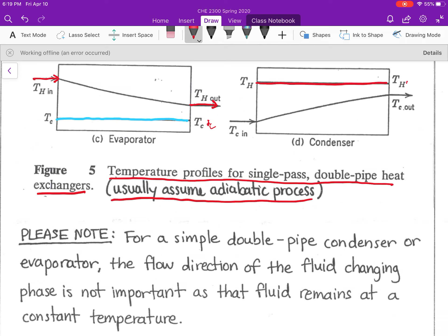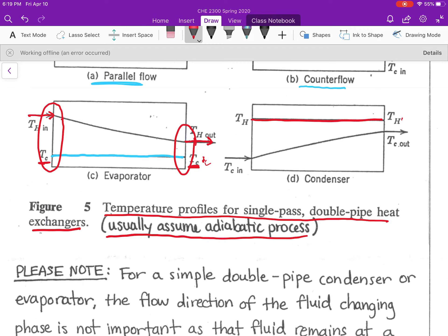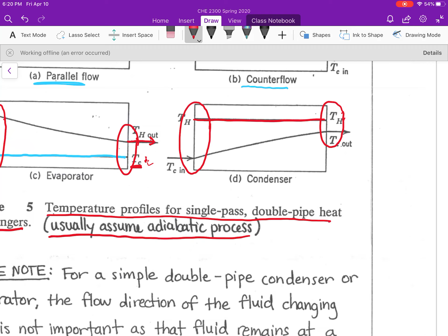It's not important because that fluid remains at a constant temperature. Regardless of what direction the cold fluid enters the evaporator, the approach temperatures on either side of the heat exchanger remain exactly the same, because the cold fluid does not change temperature. Same thing in the condenser: it doesn't matter what direction I flow my hot fluid, because the approach temperature on the left-hand side of the heat exchanger will be exactly the same regardless of what direction that hot fluid enters.